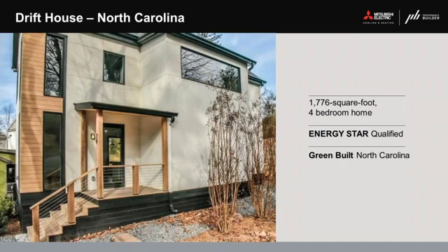Normally, if we're using wall hung units and put one in every bedroom of a newer above-code house, we'd be way oversized. Even though our systems ramp down, there's still a minimum they can reach. So in these higher performing houses, we'll put 2 or maybe 3 wall hung units in, and since the house requires ventilation, we'll use the ERV to help distribute air around the house.